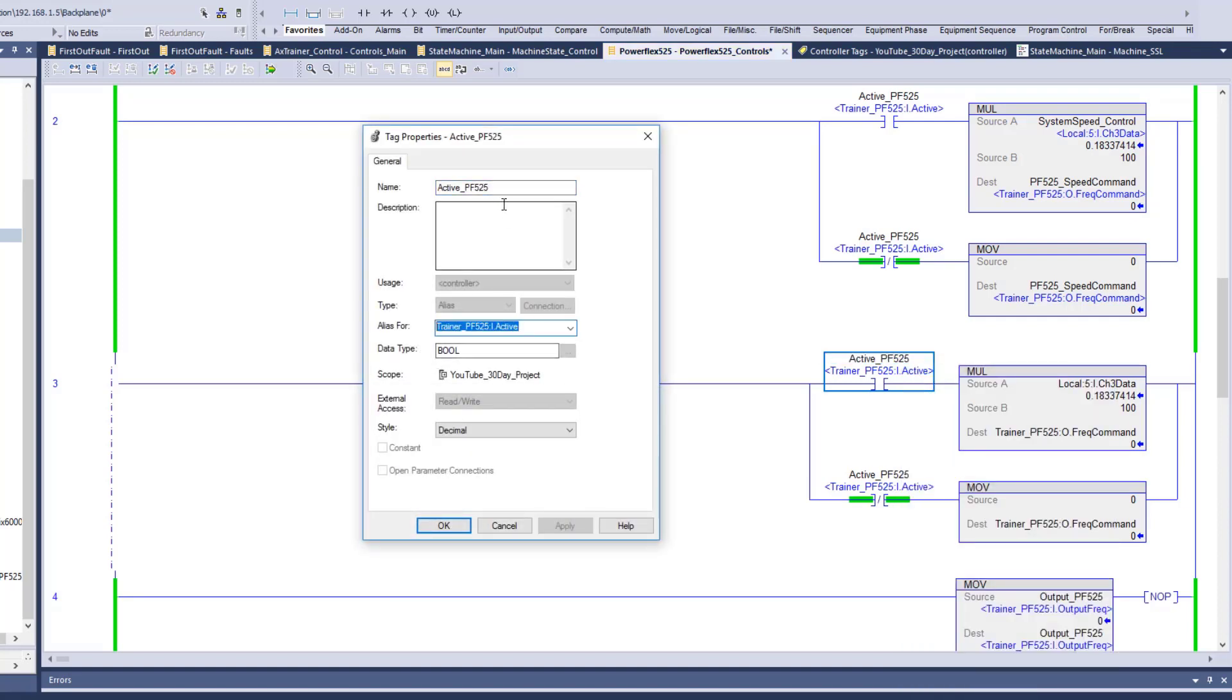All right. So we got part of it done. We're going to do this last little bit. And this active bit on the PowerFlex is just to give you a little bit of heads up. The PowerFlex has internal logic behind it on each individual device, right? So the PowerFlex 525 drive is smart enough to know when it is active and not active. If it has a start command and the actual stator of that motor is giving a torque feedback, it's smart enough to know that it's active. So that's the active bit. And that's some knowledge that you might not know.